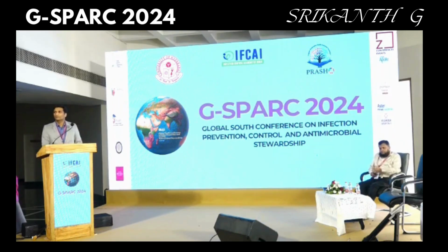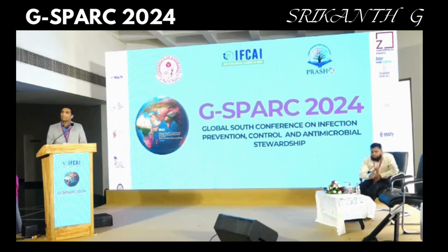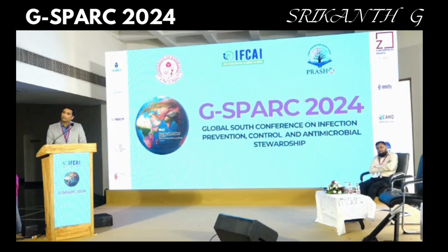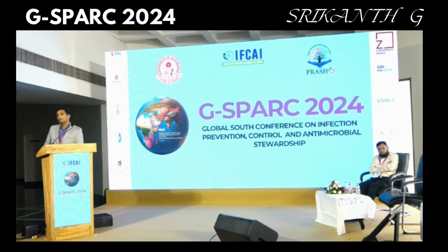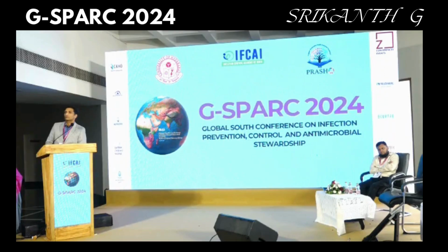Sir, I just want to add 2 points actually with the doctor. First point is regarding the reuse of the dialyzer itself. When we talk about any reuse of any medical devices, first of all, you need to look at the IFU of that equipment; how many times it can be sterilized, reused or reprocessed is mentioned in the IFU. So based on the IFU and the visible compatibility, when you see that there are no breaks and cracks in the device, till then maybe you can reuse those devices.